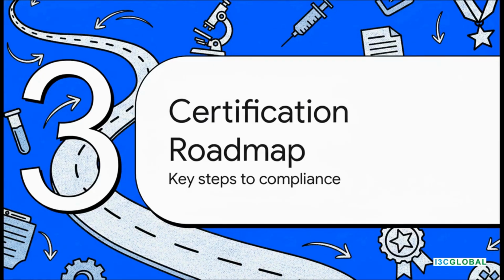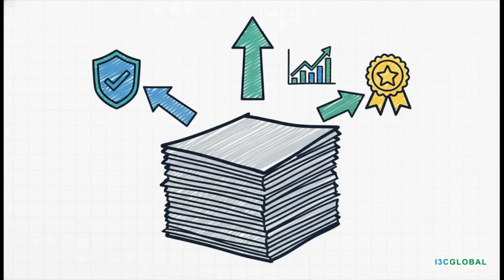All right, so we know what they are, we know why they matter. Now let's get to the good stuff. Let's map out the key steps you need to take to get these devices certified under the new rules. Here's the most crucial point. Everything, and I really mean everything, hinges on your technical documentation. This is so much more than just paperwork.